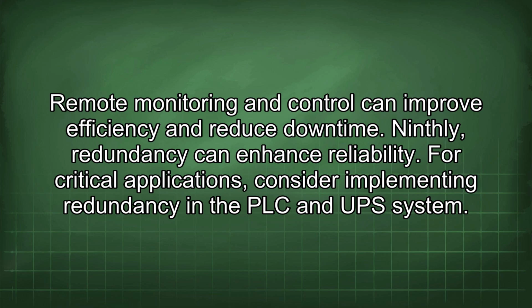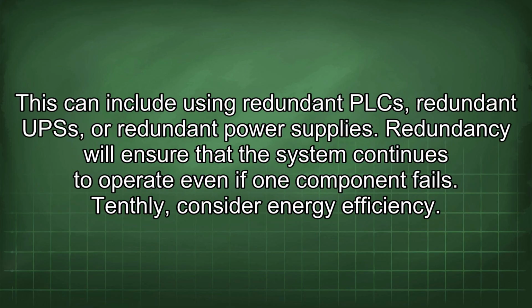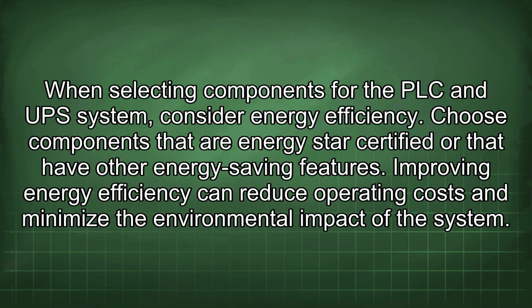Ninthly, redundancy can enhance reliability. For critical applications, consider implementing redundancy in the PLC and UPS system. This can include using a redundant PLC, redundant UPS, or redundant power supplies. Redundancy will ensure that the system continues to operate even if one component fails. Tenthly, consider energy efficiency. When selecting components for the PLC and UPS system, consider energy efficiency. Choose components that are ENERGY STAR certified or that have other energy-saving features. Improving energy efficiency can reduce operating costs and minimize the environmental impact of the system.